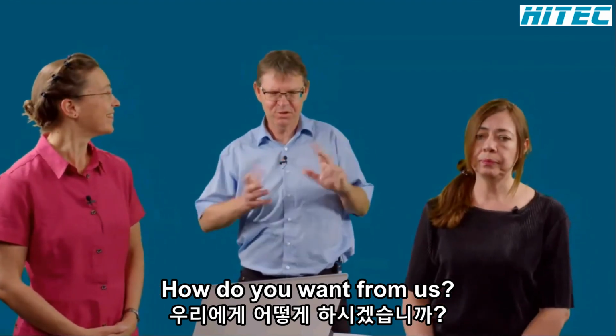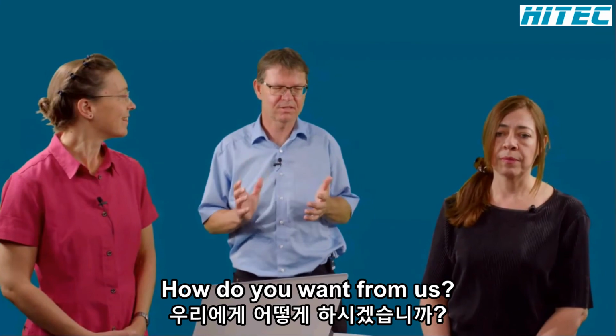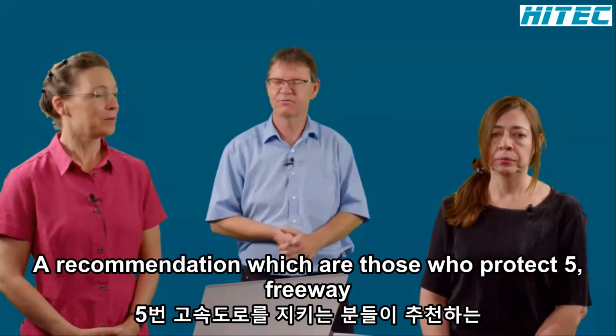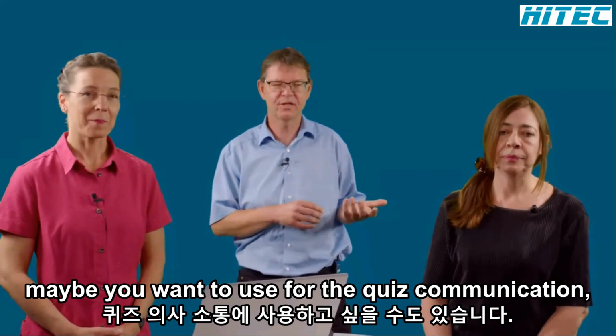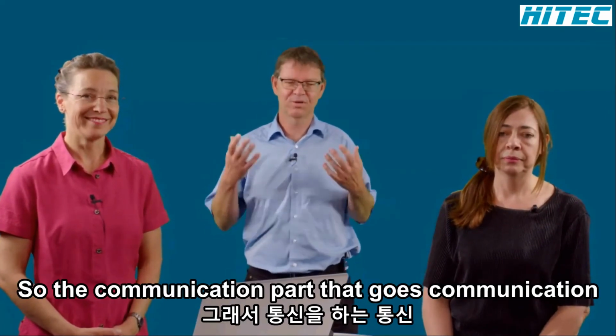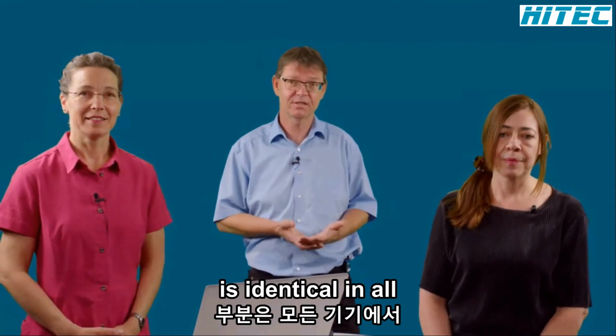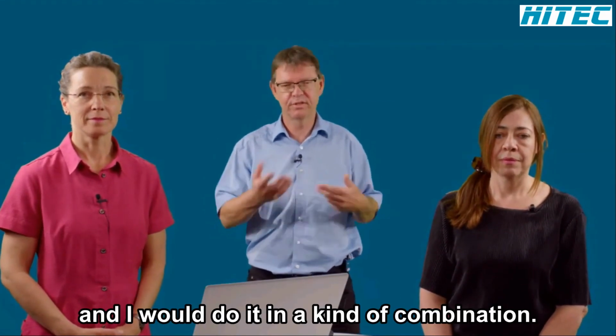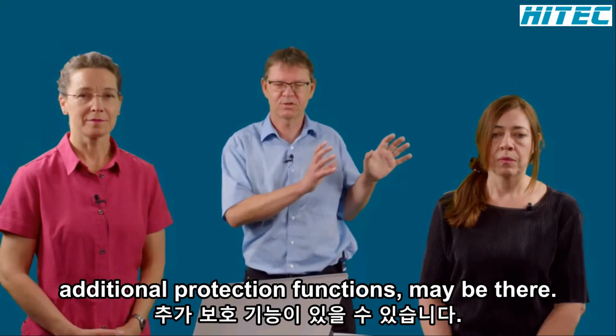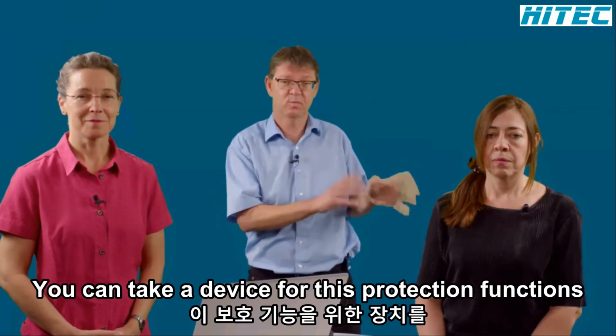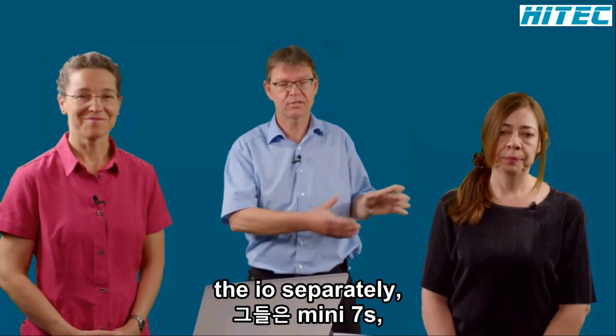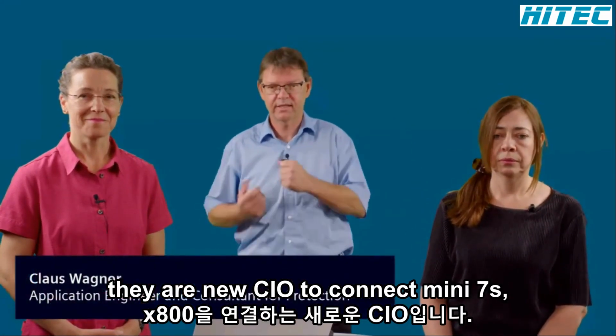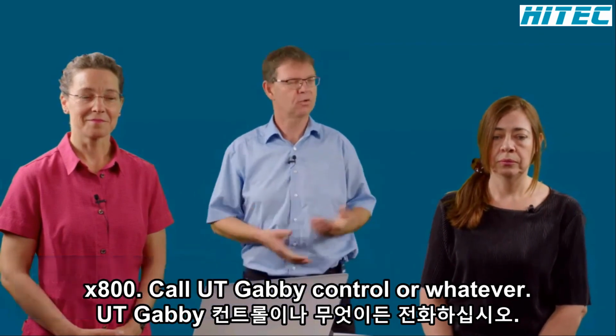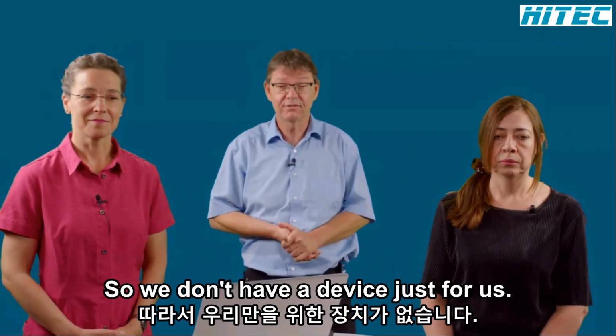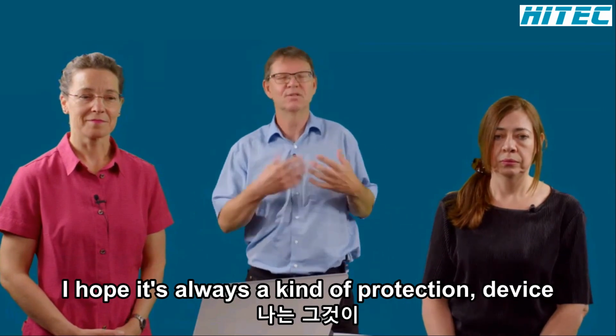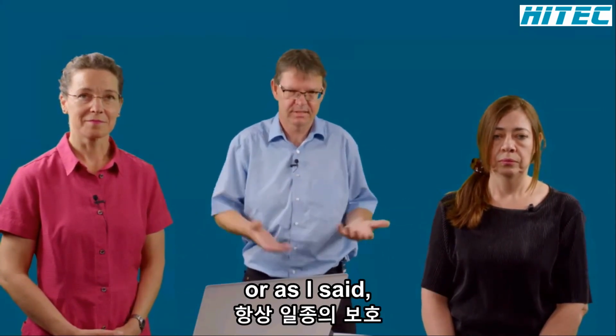I understood the question: you want a recommendation of which other SIPROTEC 5 relay you may want to use for the GOOSE communication. It's up to you. The GOOSE communication is identical in all the devices, and I would do it in a kind of combination. If you want additional protection functions, you can take a device for these protection functions and have the I/O separately there and use the I/O to connect with the 7SX800, or you take a Bay controller or whatever. We don't have a device just for GOOSE I/O. It's always a kind of protection device, or as I said, a Bay controller.